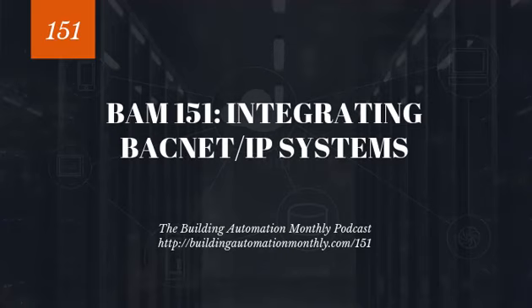And because of this issue, we will have basically opposing systems. So you'll make a command in the BAS, and then on the lighting system, maybe something goes on with a schedule or a local touch panel, and that opposes whatever command you've made in the BAS system. And so now you've got this nightmare scenario.